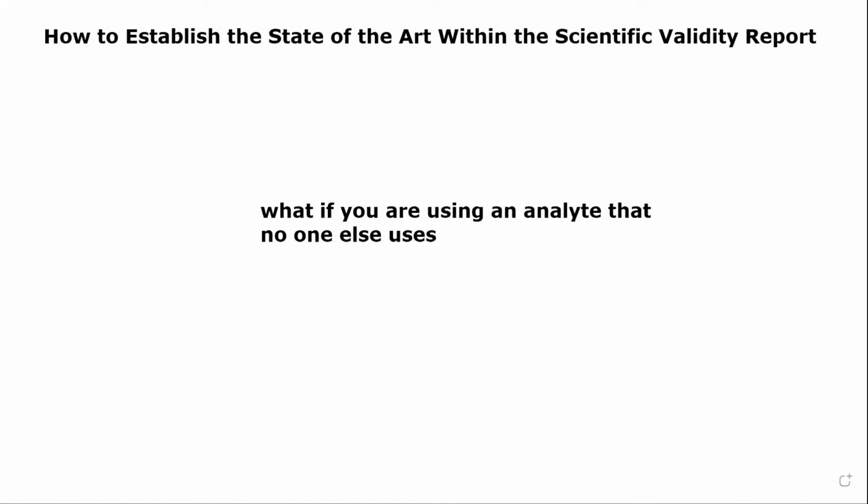we've relied on culturing these microbes, and now there's a PCR-based test. Your analyte is now a gene in that particular microbe. So as you're justifying your choice of that PCR target, that analyte, you have to show what is any potential for cross-reactivity. Are there any potential interferences with that analyte that may result in a false positive or a false negative? How specific is that analyte to the clinical condition that you've identified? And are there ways in which that analyte might not be the best target for that particular diagnosis?